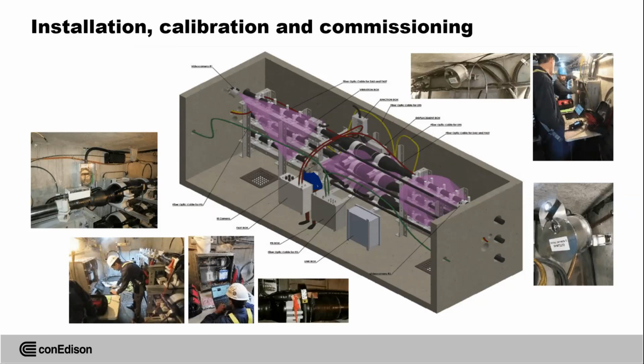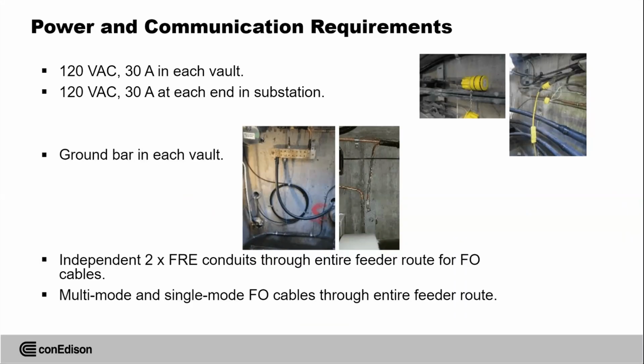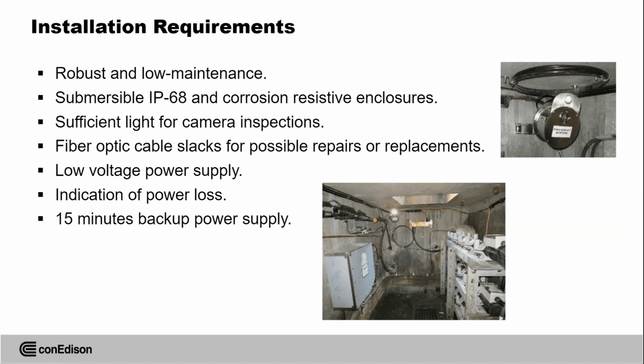Very important for fiber optic system by itself, because we run fiber optic system in separate duct to support cable monitoring system. When we come to the manhole, we use 25 feet coil up in the corners. I think somewhere here I saw the picture. I just want to come back for a second. Right, you see here on top of camera, it's 25 feet coil fiber optic cable from both sides of the manhole. It's done just in case we need to do repair, or if a failure happened and fiber will not be damaged here because it's separate, so we can resplice it.